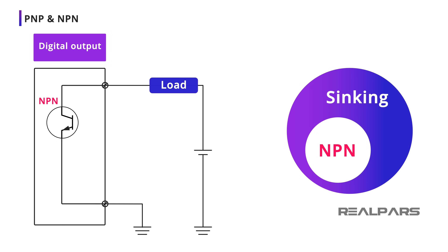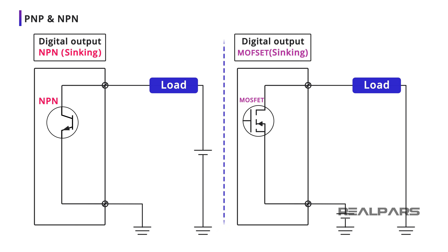If a PLC output module is listed as an NPN type, you can be sure that it is a sinking type. But if a PLC module is listed as a sinking type, it may or may not be an NPN type. Many vendors use other solid state devices such as MOSFETs to perform the switching.